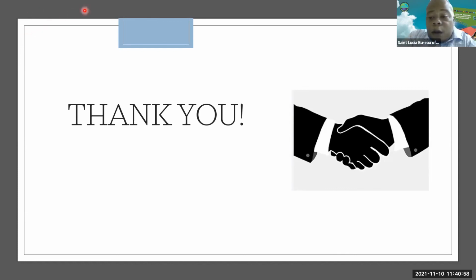Okay, thank you. Mr. Gittins, go ahead. In St. Lucia, our domestic voltage supply is 240 volts, but many persons wire their homes for 120 volts by installing a transformer. Based on complaints over the years, we've found that inefficient, because transformers consume a lot of energy even when not loaded. Ideally, one should have appliances rated for 240 volts, connected directly to the local grid.